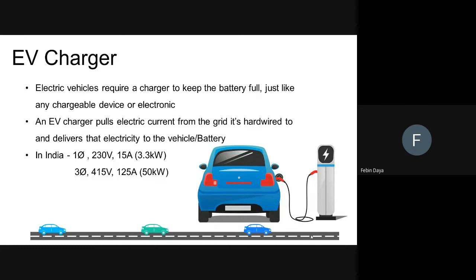On the other hand, if I go for three phase supply, Indian grids supply voltage at 415 line to line, and the maximum current I can draw is 125 ampere. So with three phase supply, I can go for a charger which is about 50 kilowatts. So single phase maximum 3.3 kilowatts.